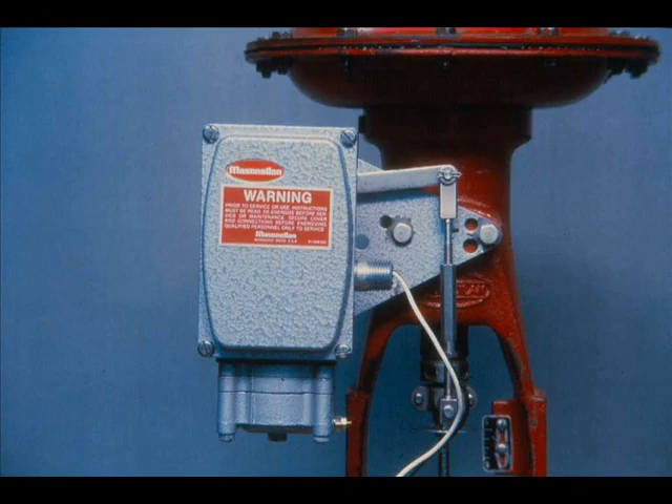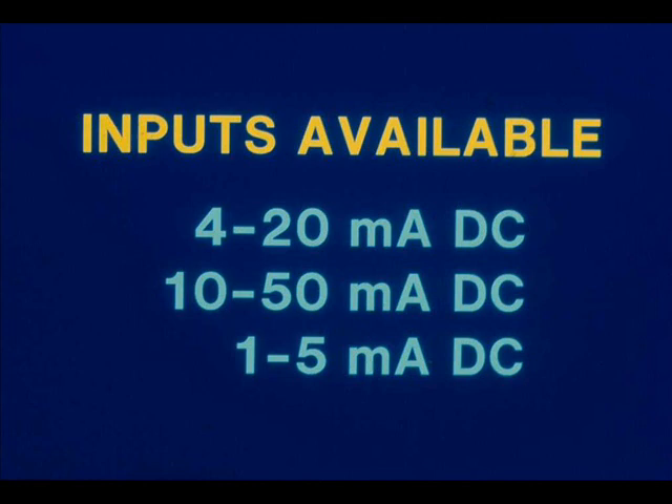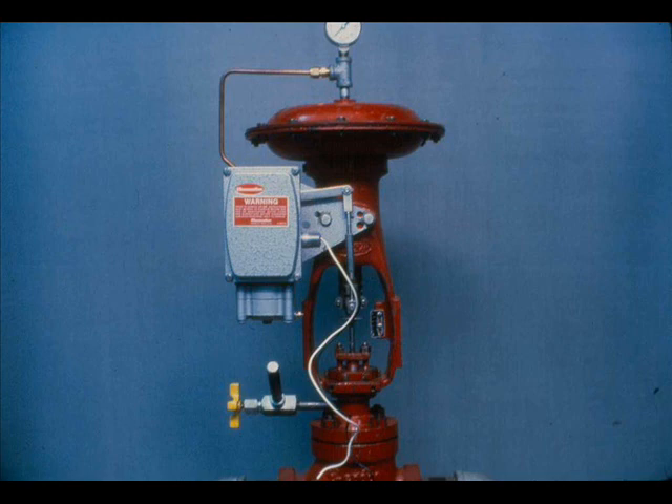The Masoneilan Model 8012 is an electro-pneumatic valve positioner. It provides an accurate means of obtaining a valve stem position proportional to a 4 to 20 milliamp DC input signal. Besides the 4 to 20 milliamp input range, it is also available for input ranges of 10 to 50 milliamps and 1 to 5 milliamps. The current input produces a pneumatic output which positions the valve stem.